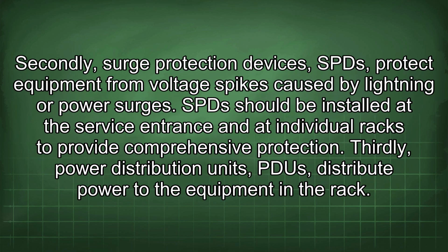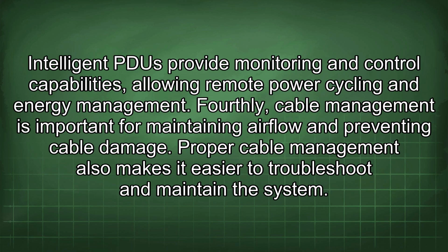Secondly, surge protection devices, SPDs, protect equipment from voltage spikes caused by lightning or power surges. SPDs should be installed at the service entrance and at individual racks to provide comprehensive protection. Thirdly, power distribution units, PDUs, distribute power to the equipment in the rack. Intelligent PDUs provide monitoring and control capabilities, allowing remote power cycling and energy management.